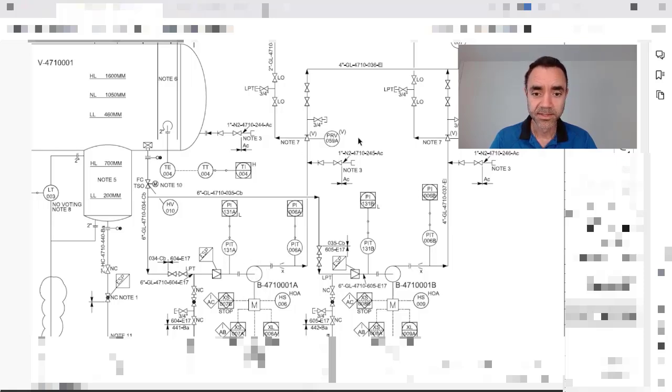transferring. In this installation here, you can see that we have a tap of utility. We have a quick connection to connect nitrogen to make sure to clean all these lines before removing the pump for maintenance, because again, it is a pump installed with a flammable fluid service, and to prevent any kind of incident or accident, it's important to inert all the circuit before opening it to atmosphere.